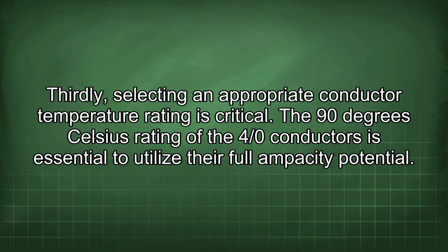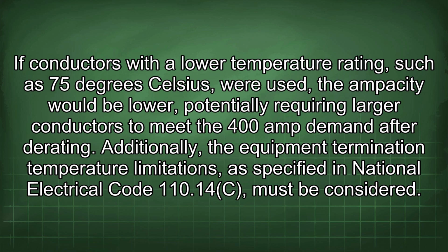Thirdly, selecting an appropriate conductor temperature rating is critical. The 90 degrees Celsius rating of the 4/0 conductors is essential to utilize their full ampacity potential. If conductors with a lower temperature rating, such as 75 degrees Celsius, were used, the ampacity would be lower, potentially requiring larger conductors to meet the 400 amp demand after derating.